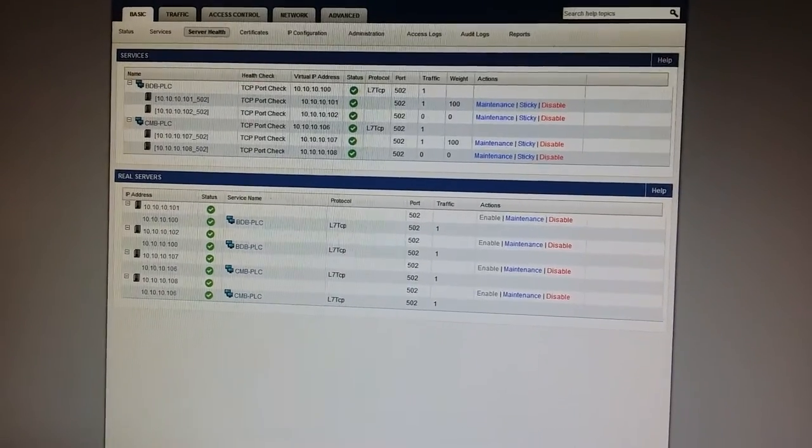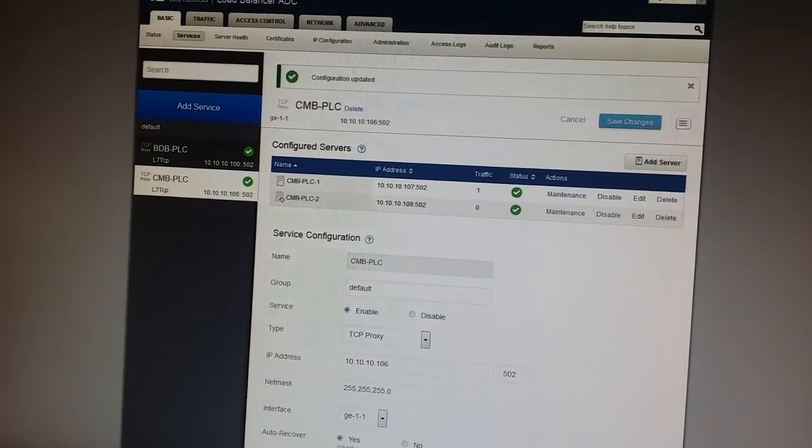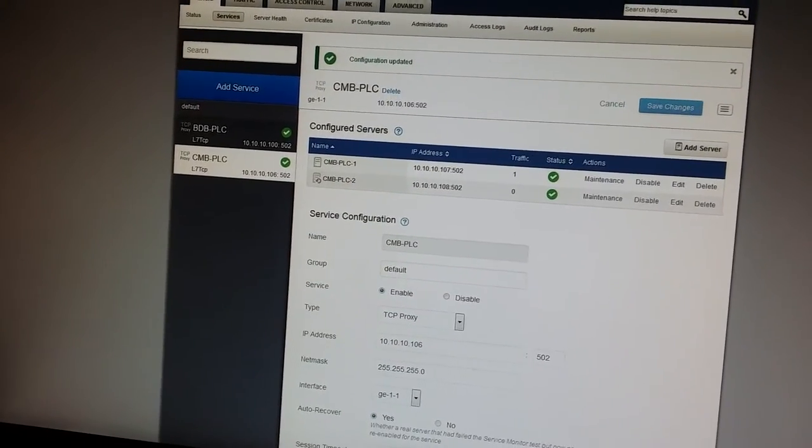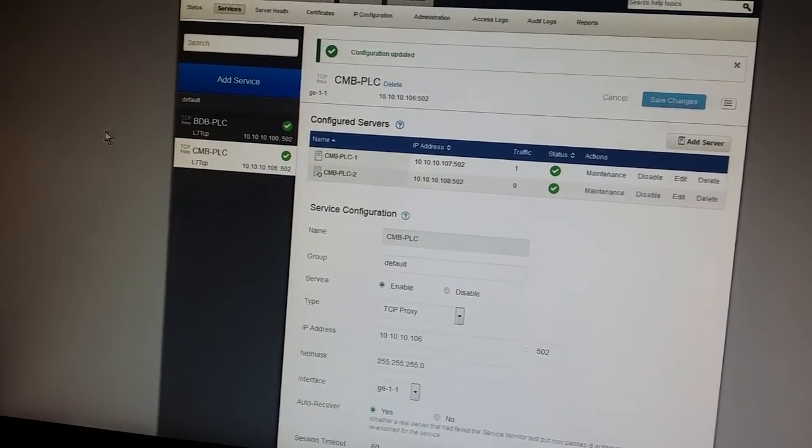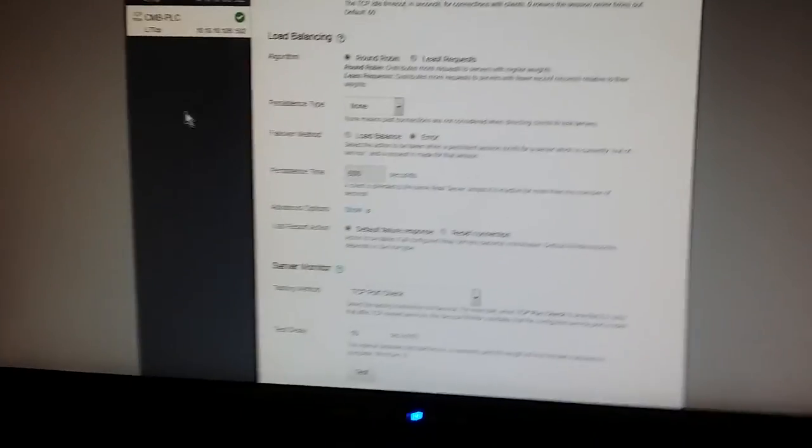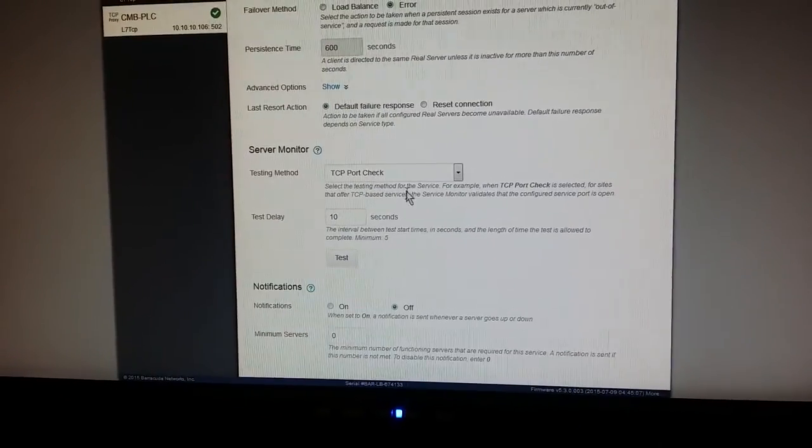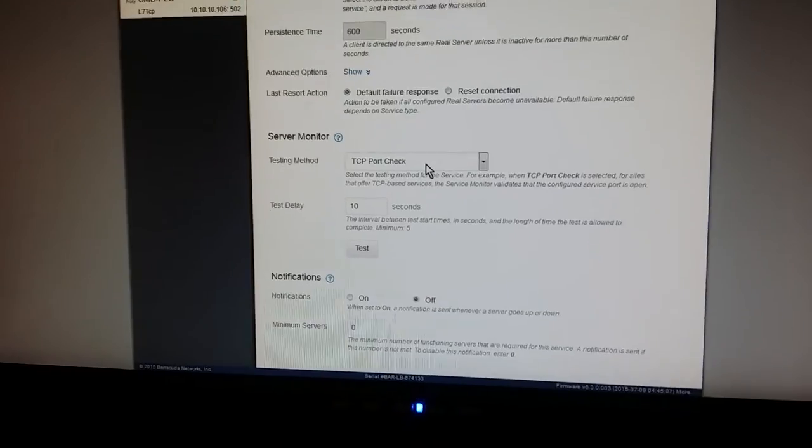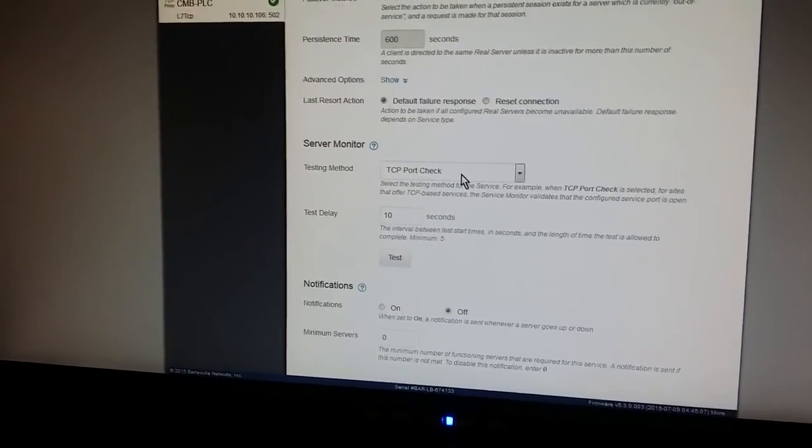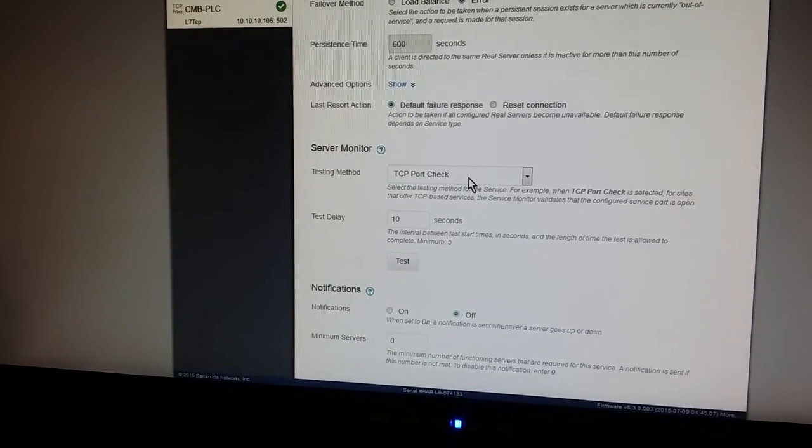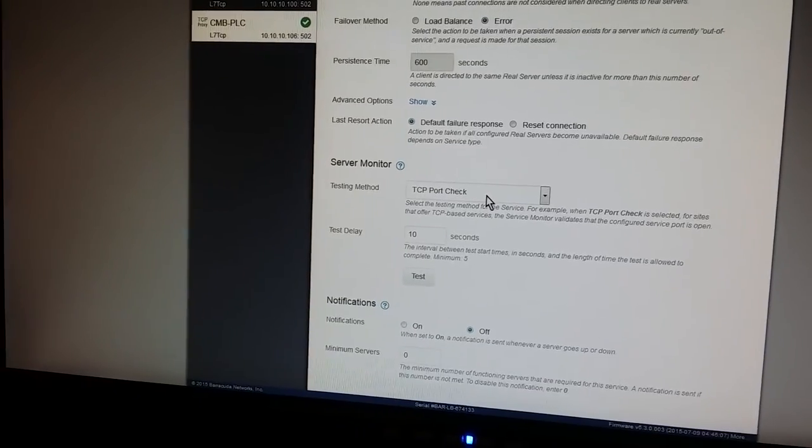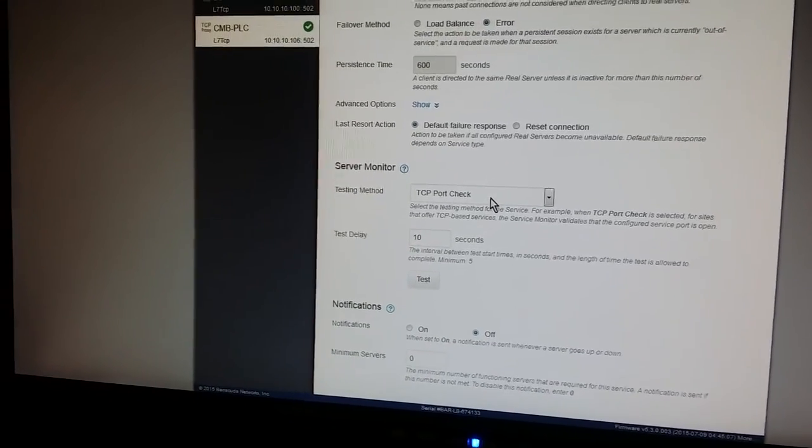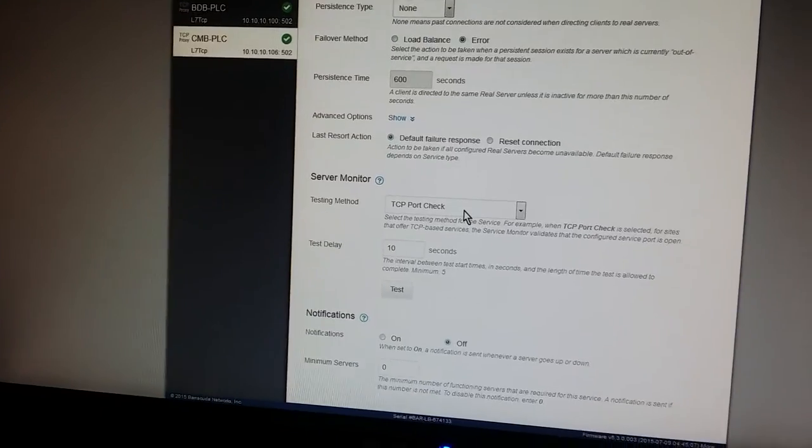The Barracuda checks the life of the two PLCs not with ping but better by actually connecting to the hosting port socket using a TCP port check. In this case port 502. So it's not enough for just the thing to be pinging. The Modbus stack needs to be responding as well to be qualifying as functional.